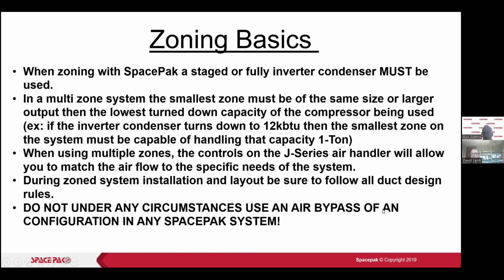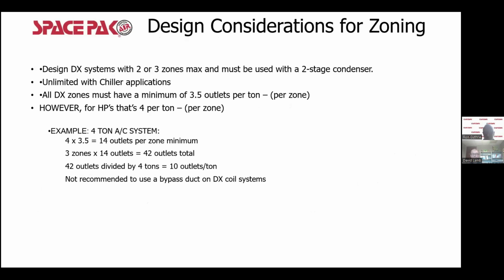All right, never use an air bypass. You're going to freeze our system. You could freeze a conventional system, but you're going to freeze our system, and it's not going to work right. It's actually going to go off on the freeze control.